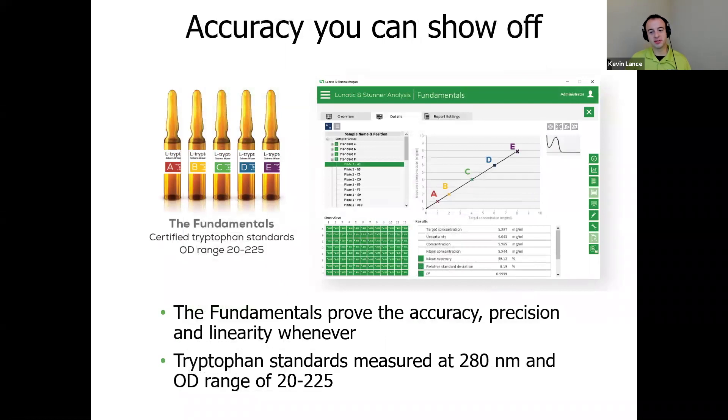The UV-Vis of Stunner is also shockingly accurate, and Stunner loves to prove it. So using the fundamentals tryptophan standards, the accuracy, precision, and linearity of the instrument can be proven at any time across the OD range of 20 to 225. So you can be confident about every sample with data that leaves no room for doubt.